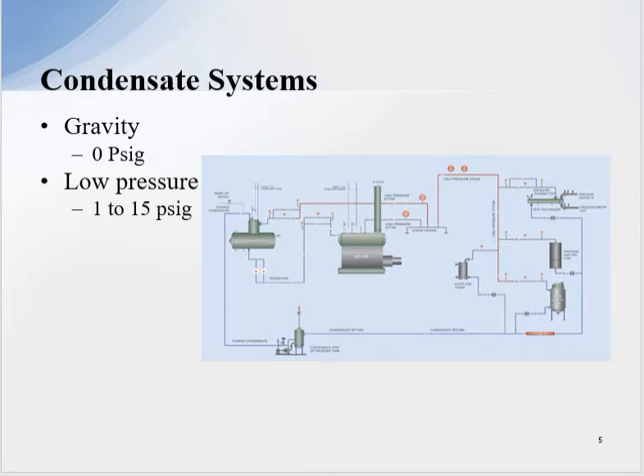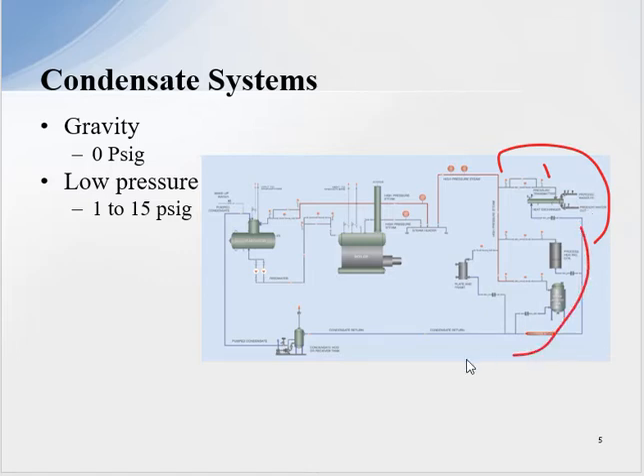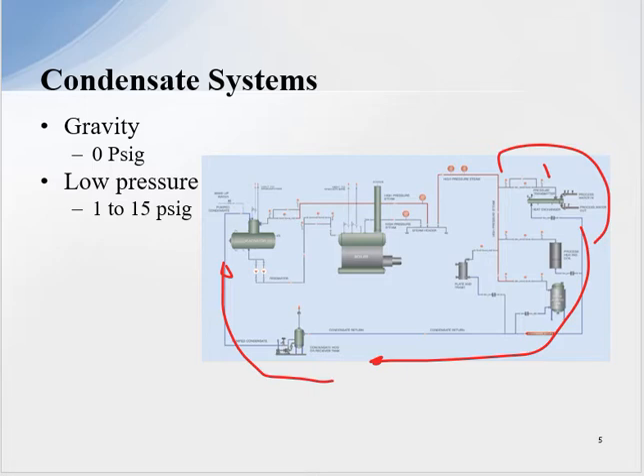On a gravity system — zero PSI or low pressure up to fifteen PSI — if we have a process that modulates steam, the steam to the process can be as low as zero PSI. Then the condensate needs to come down by gravity to a pumping unit, because we have to deliver it either back to the boiler plant or back to the deaerator. With those types of processes, they cannot tolerate any pressure.